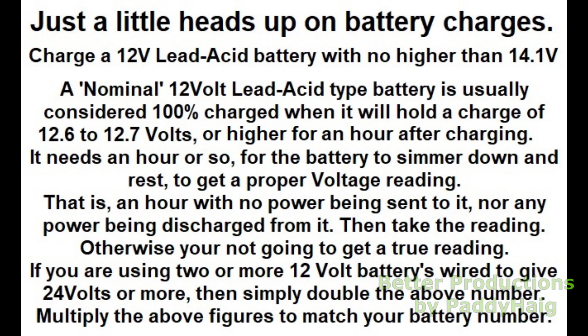Keep in mind that regular 12-volt nominal lead-acid batteries usually accept a charge voltage of between 12 and 14.1 volts. A lead-acid battery is fully charged when, after a 1 hour resting period of not being charged or discharged, it holds a stable 12.6 to 12.7 volts.